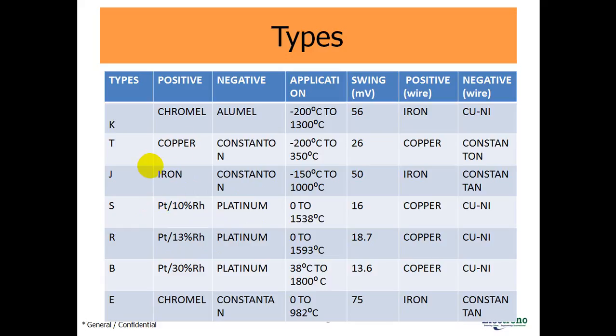Type R: the negative lead is made by platinum. Application is 0°C to 1593°C, voltage swing is 18.7 millivolts, positive wire is copper, negative wire is copper-nickel. Type B: platinum is 70%, rhodium is 30%. Negative lead is made by platinum. Application is 38°C to 1800°C, voltage swing is 13.6 millivolts, positive wire is copper, negative wire is copper-nickel. Type E: positive lead is made by Chromel, negative lead is made by Constantan. Application is 0°C to 982°C, voltage swing is 75 millivolts, positive wire is iron, negative wire is Constantan.